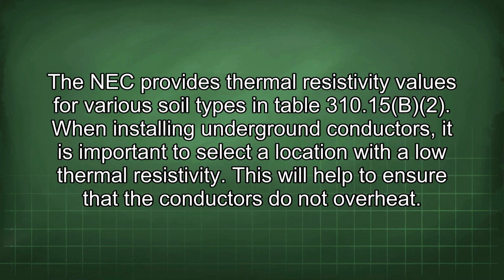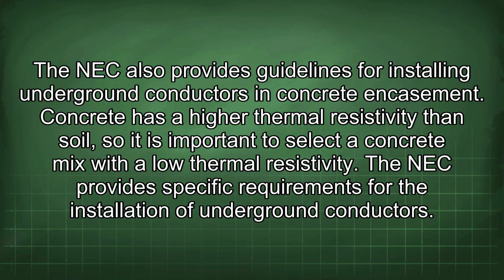The NEC provides thermal resistivity values for various soil types in Table 310.15(B)(2). When installing underground conductors, it is important to select a location with a low thermal resistivity. This will help to ensure that the conductors do not overheat. The NEC also provides guidelines for installing underground conductors in concrete encasement.